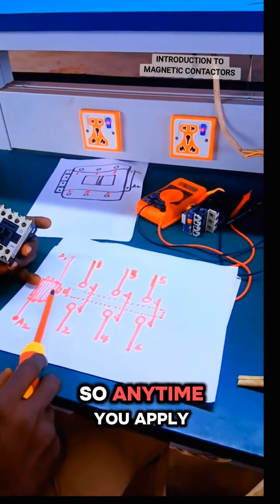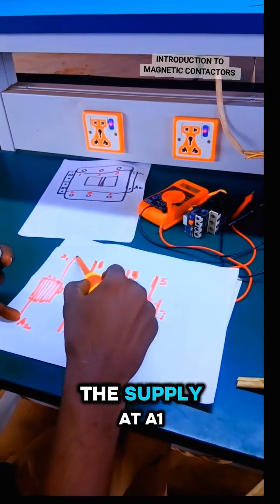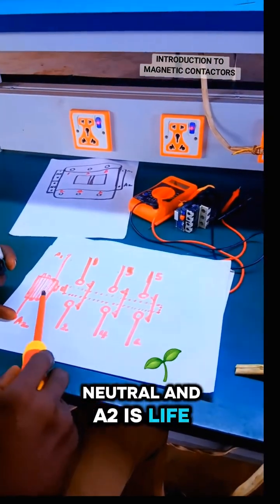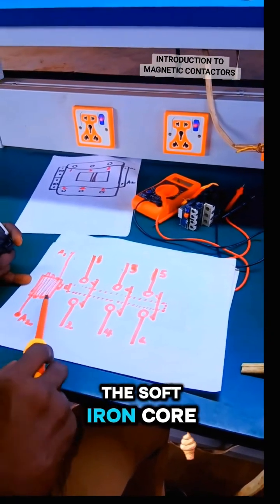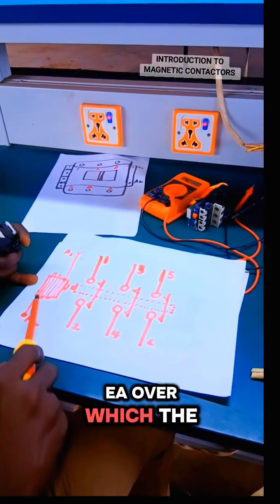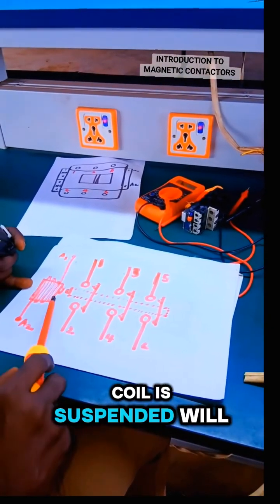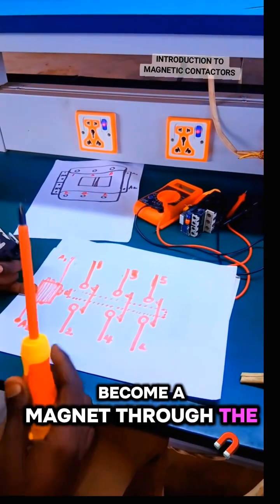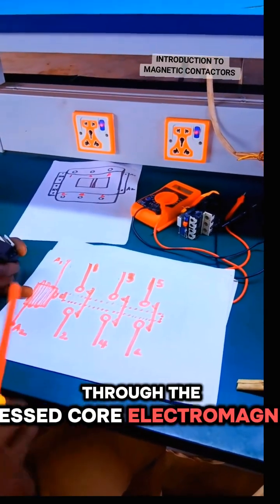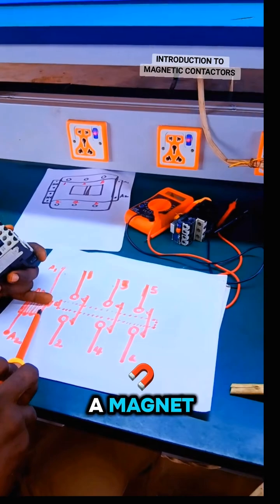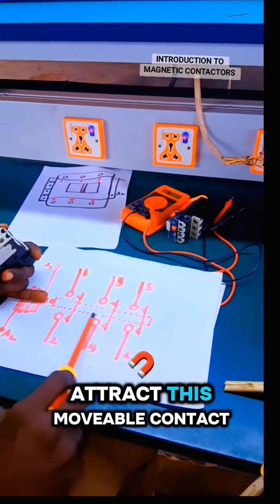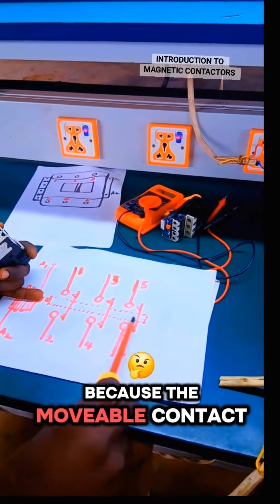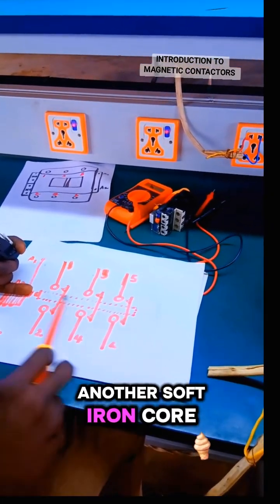Anytime you apply the supply at A1 and A2, let's say A1 is neutral and A2 is live, what happens is that the soft iron core here, over which the coil is suspended, will become a magnet through the process called electromagnetism. And when it becomes a magnet, it is going to attract this movable contact, because the movable contact is also built on another soft iron core.